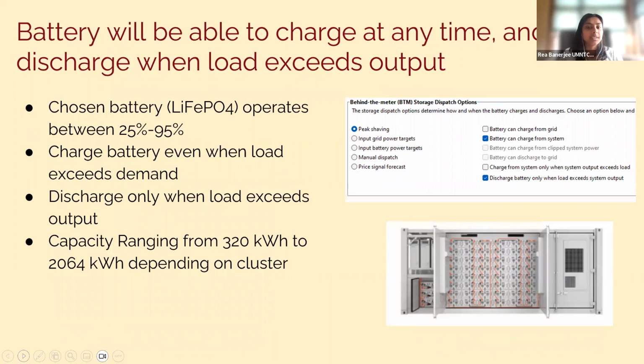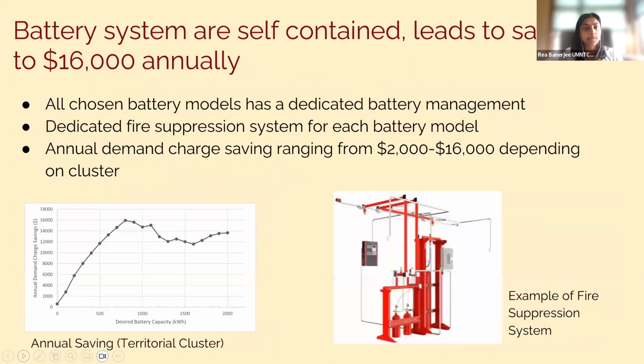With the high load of the buildings on campus, the batteries will be able to charge at any time and discharge when the load exceeds system output. Depending on the cluster, ideal battery capacities range from 320 kilowatt hours to 2064 kilowatt hours. Our chosen battery model is fully self-contained and hosts its own battery management system, as well as a fire suppression system, allowing the selected battery to be placed in building penthouses or outside, depending on the size of the battery.